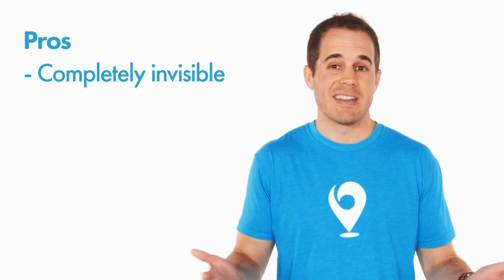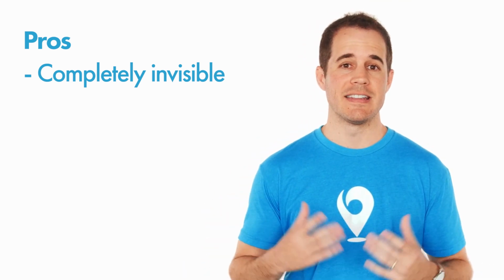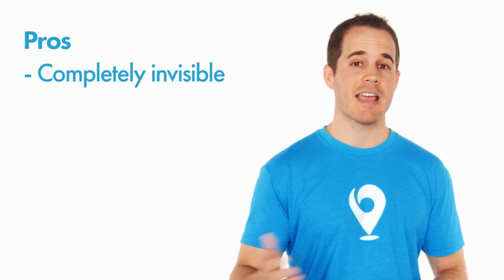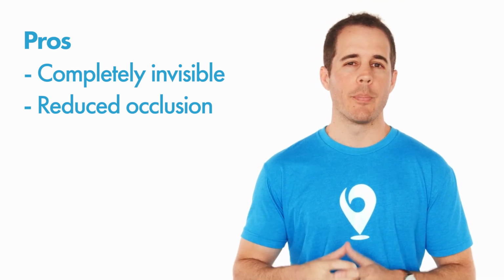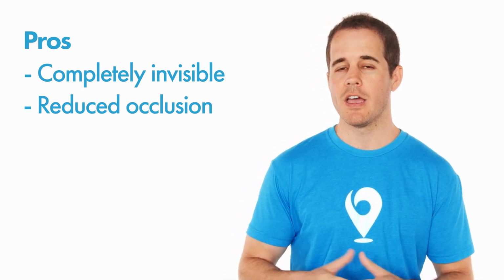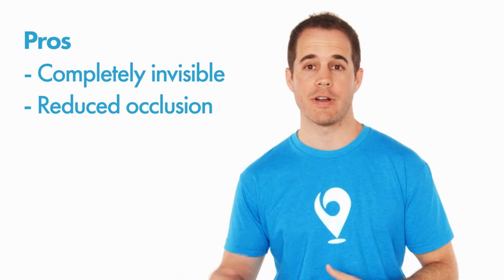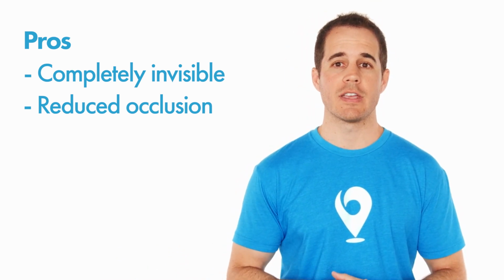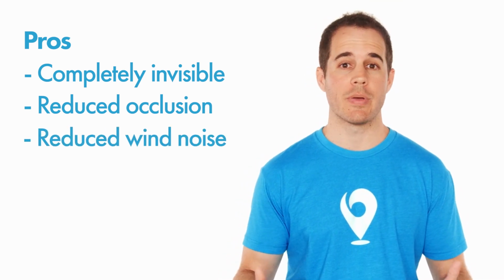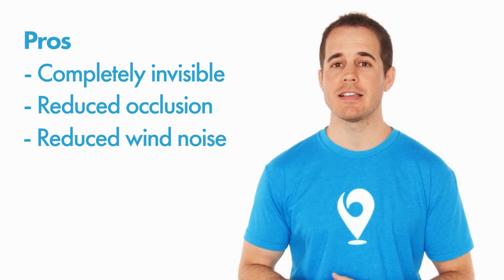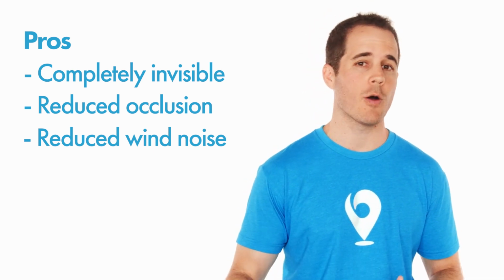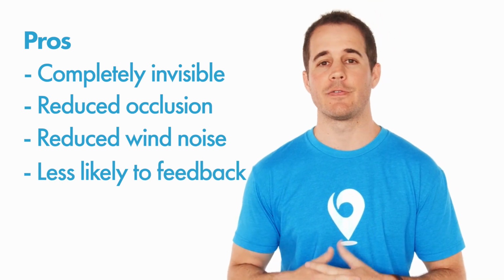So for the pros, the main reason people buy these is they are as invisible as you can get. You know, nothing behind the ear, everything sits deep inside the ear canal. Because everything sits so deep in the ear, you won't get as much of the occlusion effect when you wear these hearing aids. I'll put a link below about the occlusion effect, but basically, when you wear IICs, you don't feel as plugged up as compared to when you wear other in-the-ear devices. Another benefit of them being so deep is that the microphones on the hearing aids are protected from the wind, so the microphone doesn't pick up a lot of wind noise. And then finally, because they sit so close to your eardrum, they use less power than other devices and are then less likely to feedback and whistle.